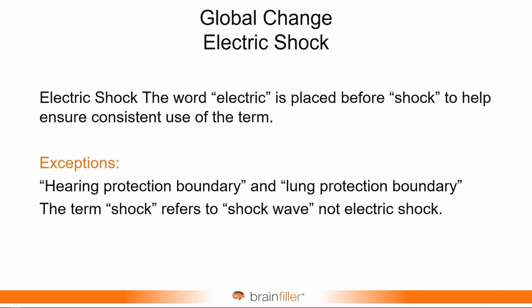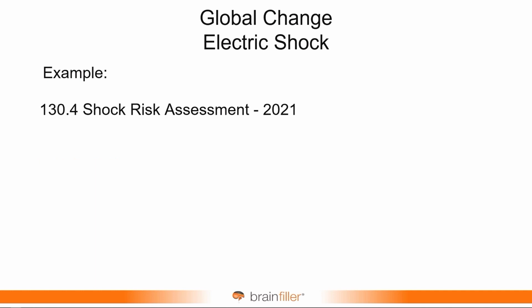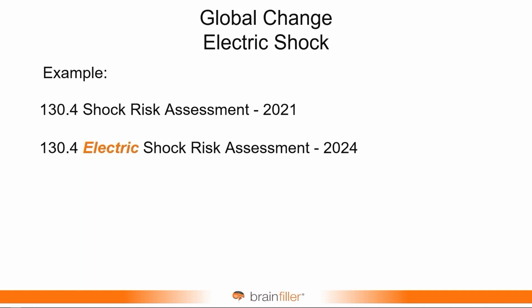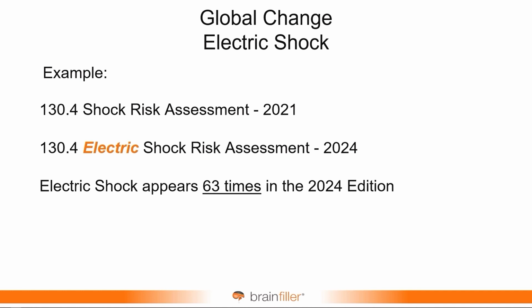But there are some exceptions, two exceptions actually. There is what is known as a hearing protection boundary and a lung protection boundary. Both of these terms use the word shock. In these cases, they're referring to shock wave, not electric shock. So now, places where you see shock risk assessment, it now says electric shock risk assessment. Anywhere you see shock, you see it preceded with the word electric, except for the two exceptions. Electric shock appears 63 times in the 2024 edition. So this was quite a sweeping change within NFPA 70E.